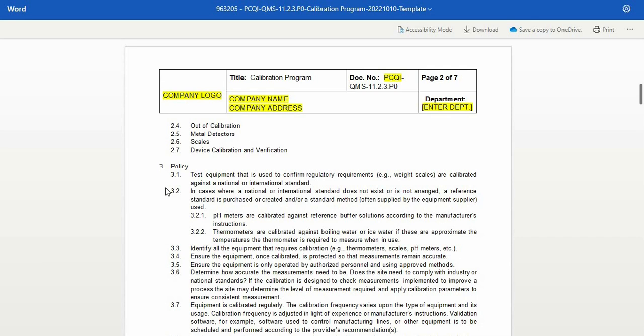Second, in cases where a national or international standard does not exist or is not arranged, a reference standard is purchased or created and/or a standard method, often supplied by the equipment supplier, is used. pH meters are calibrated against reference buffer solutions according to the manufacturer's instructions. Thermometers are calibrated against boiling water or ice water if these approximate the temperatures the thermometer is required to measure when in use. Third, identify all the equipment that requires calibration, for example, thermometers, scales, pH meters, etc.